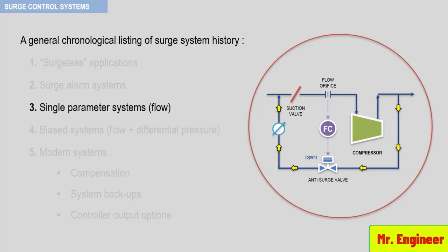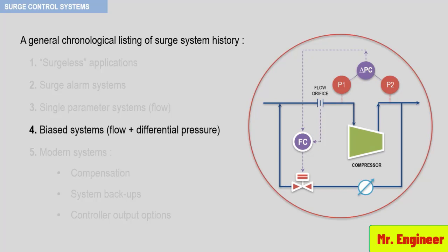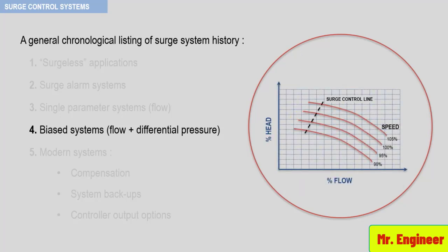The next system shown here is the standard two-parameter or biased system that has been employed almost exclusively in the industry over the past years. This system, as you can see here, consists of flow measurement and differential pressure measurement across the compressor and results in a surge control line that roughly parallels the actual surge line of the compressor. It allows operation across a wider range than the single parameter system and, if properly sized, can perfectly protect the compressor.